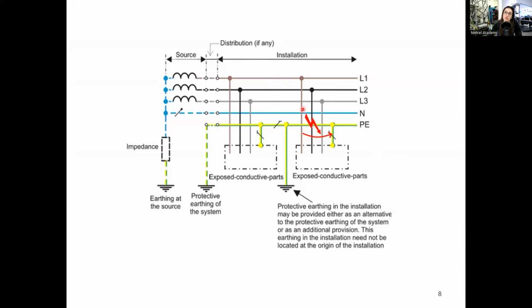This diagram also shows how this breaks the isolation of the system. So now both the general earthing of the wider system and the isolated part of the earthing are connected, and the whole system works as a TN grounding system. Now, in IT systems, the limit for installation leakage is usually relatively low, and this enables us to work with the leakage clamp where it is the most precise, in the milliamp range.